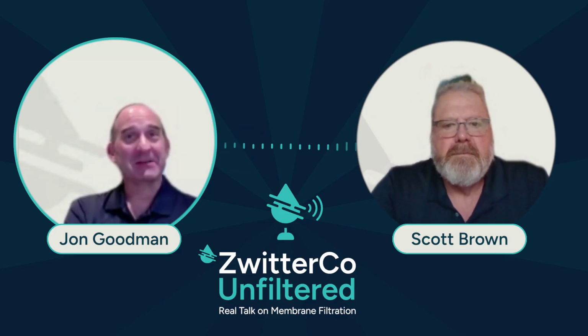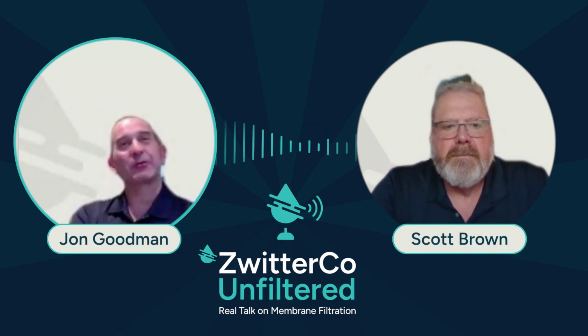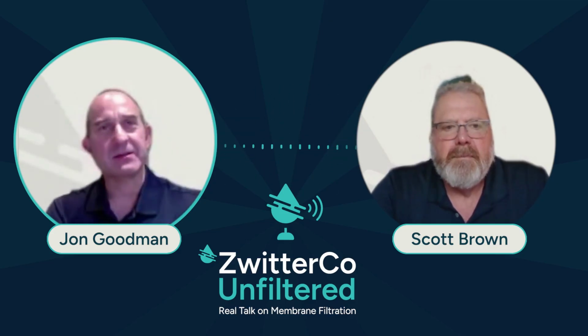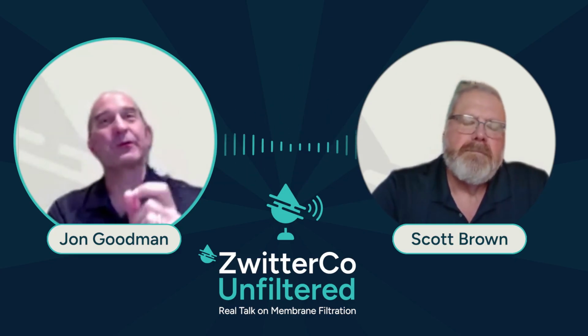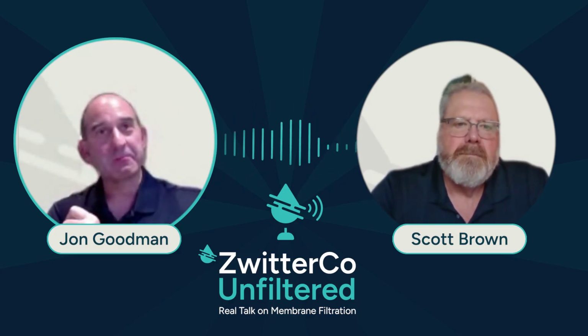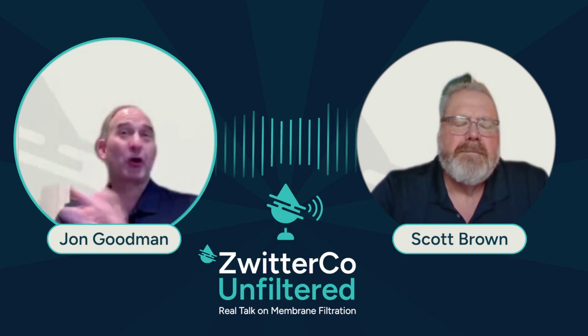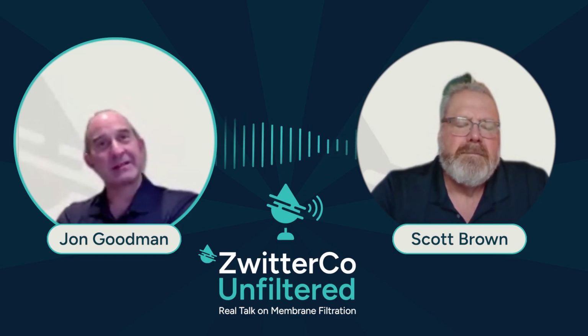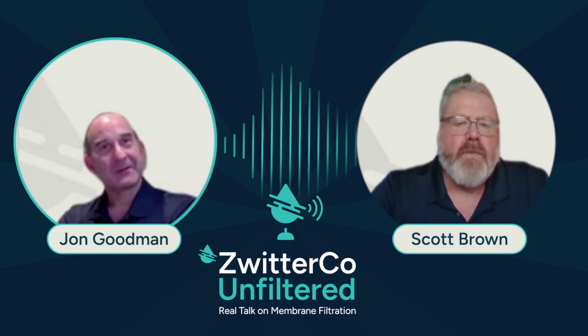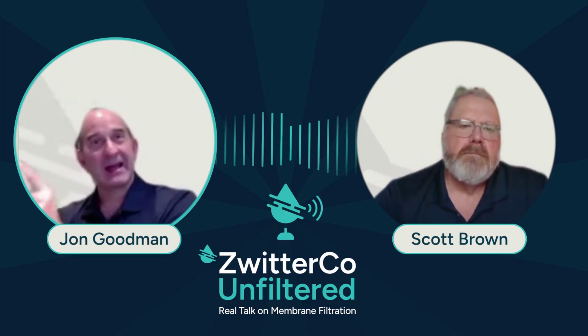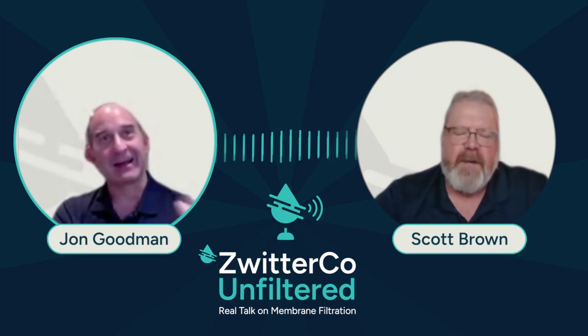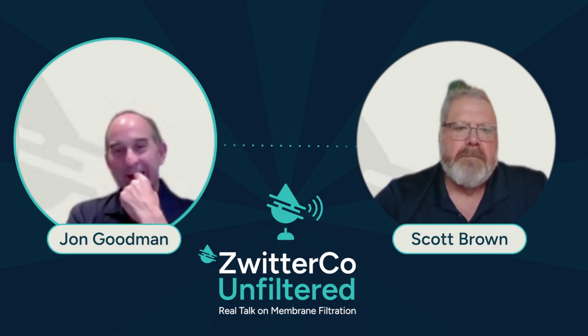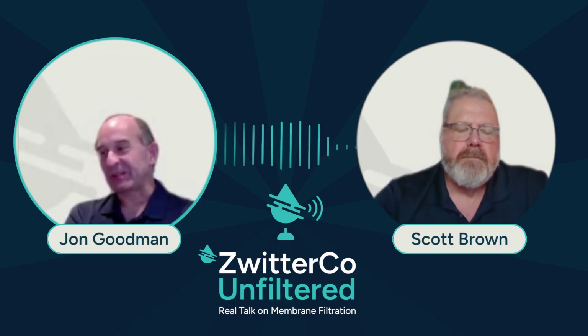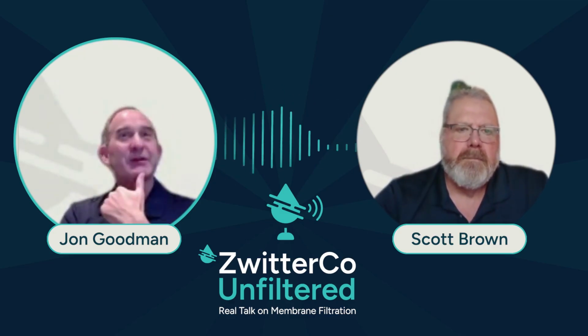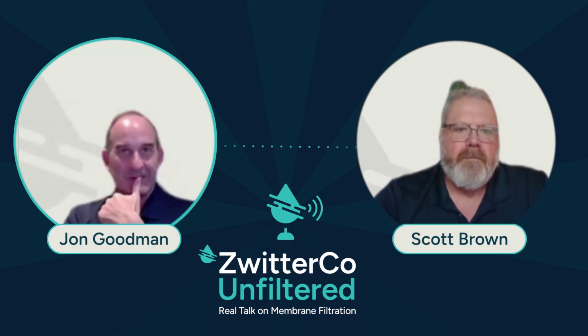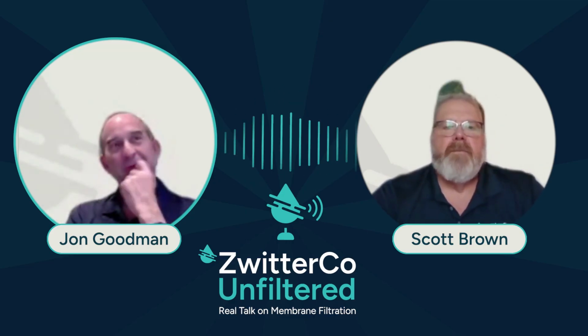So it's funny, when I was thinking of the topic, I was trying to think of some of the interesting designs. Do you remember some of the early ones, this goes back to the 1990s? One of my customers referred to it as a full Mother Nature system. To achieve higher solids in an RO system, they would put NF membranes in the final stage. Sure, we did that. And then take the permeate from the NF and put it back to the feed stage. Yep. And the biggest challenge I remember with those systems was controlling calcium phosphate scale in that NF stage. Are people still doing that system? Because I haven't heard of one in a while.